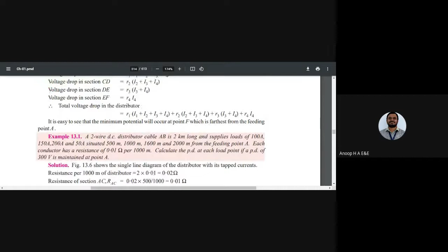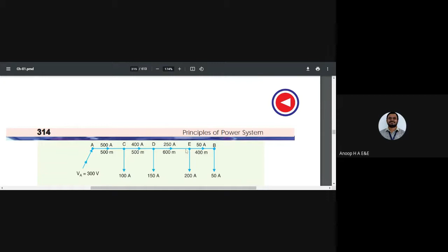So once you take the value of the current, how are you going to find out the value of the current? In the last section, you have 50 amperes of current. Observe here, we are going to take it from this section. If I get this 50 amperes, it is just like working back. So it would be 50 plus 200 at the section DE, that is 250 amperes. This 250 amperes is again added with another section current, that is 150, that is 400 amperes. Next, we have the current in AC, that is 400 plus 100, that is 500 amperes. So how did we get 500 amperes? We started from the back section, that is 50 amperes, and then we got it by back substitution.